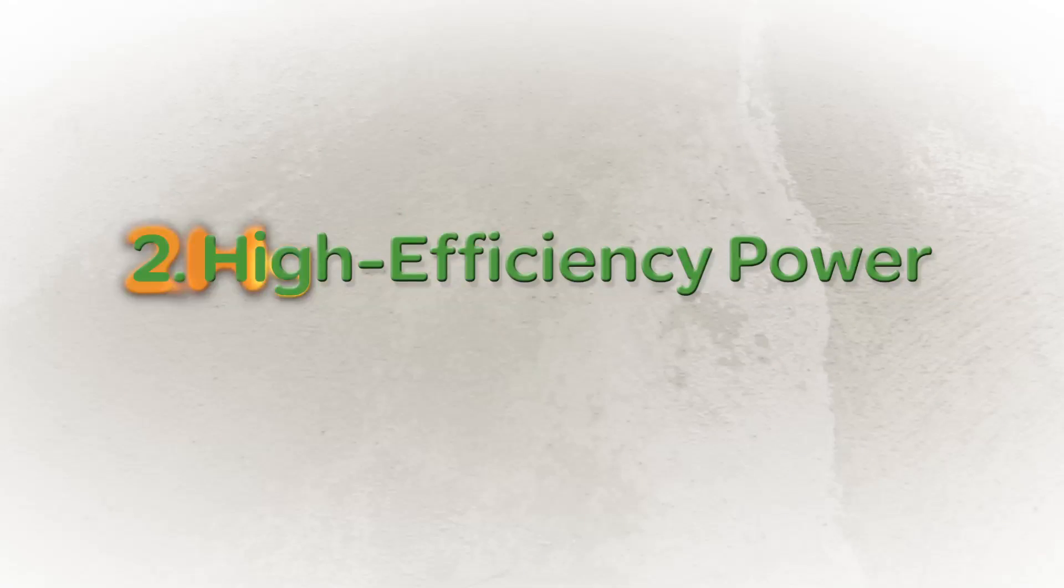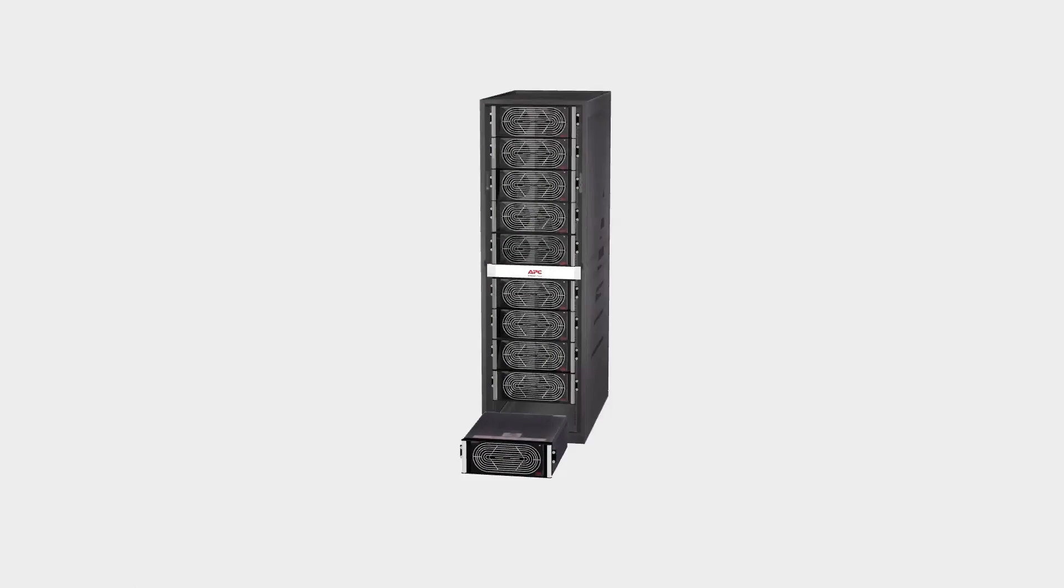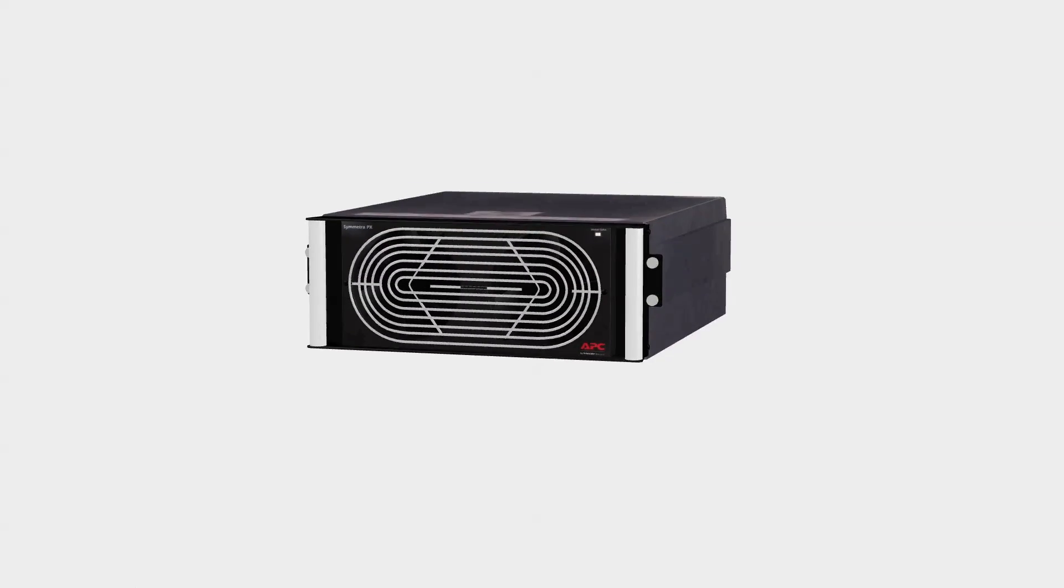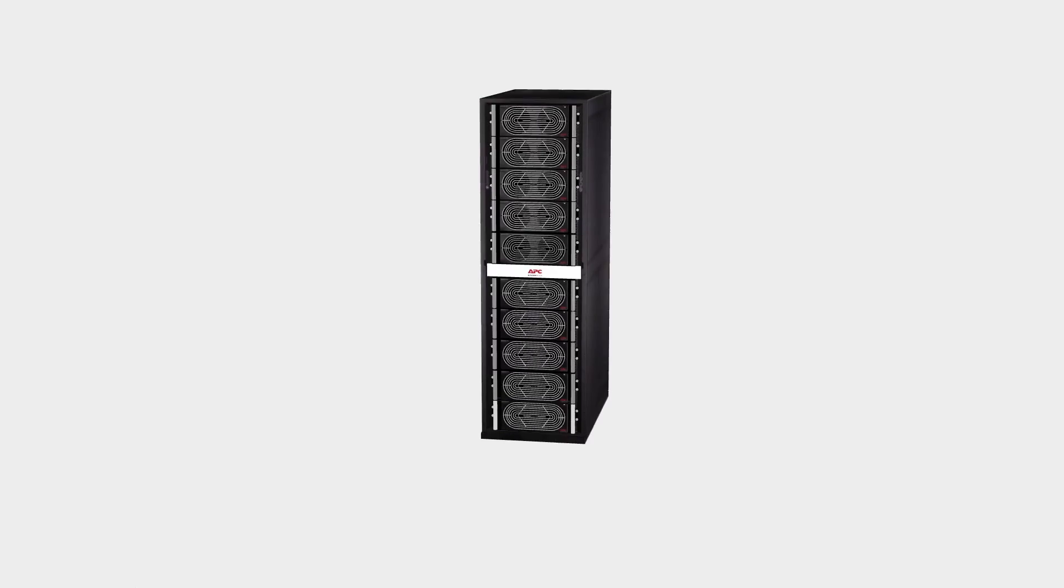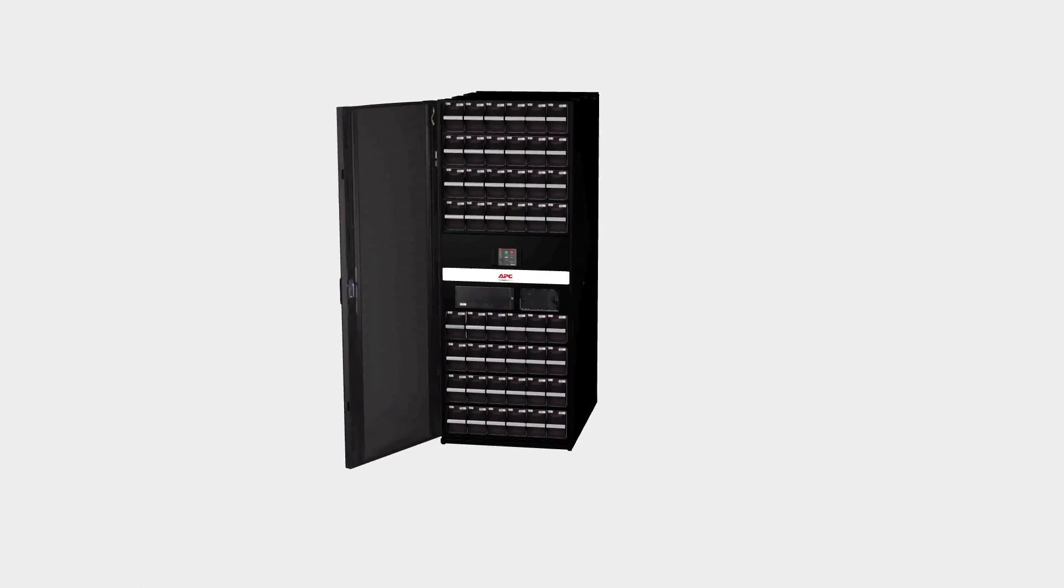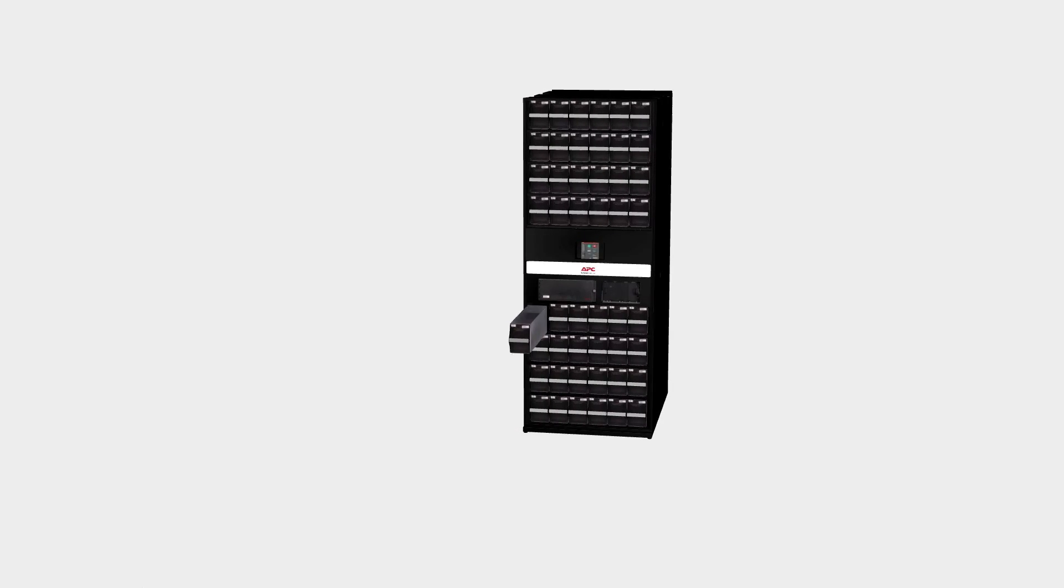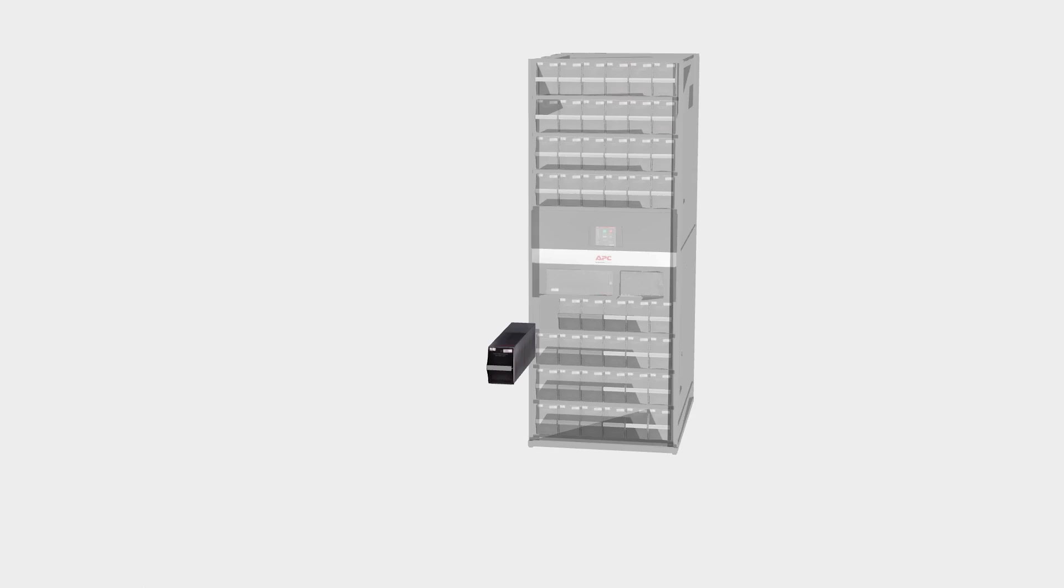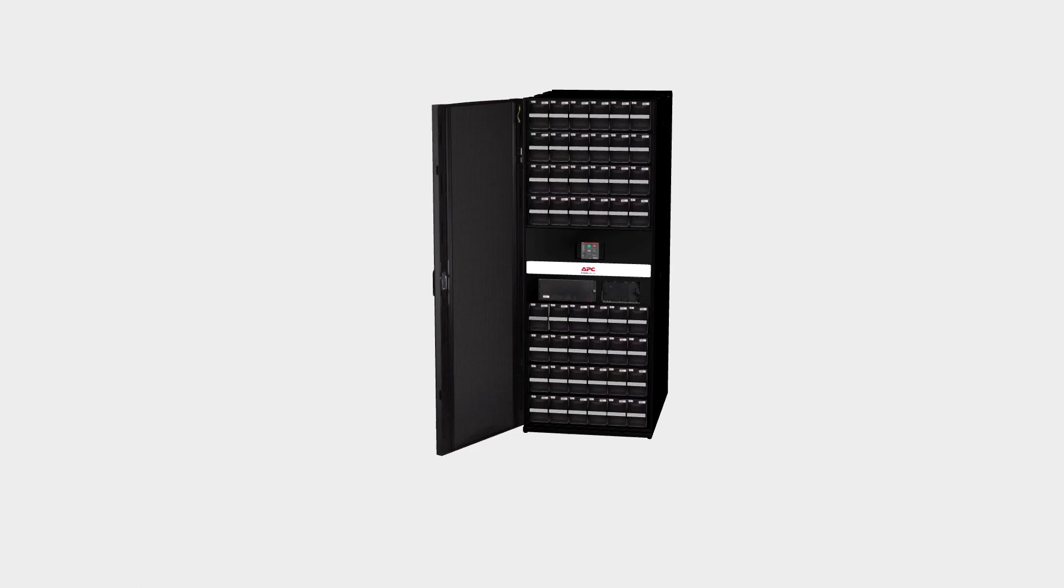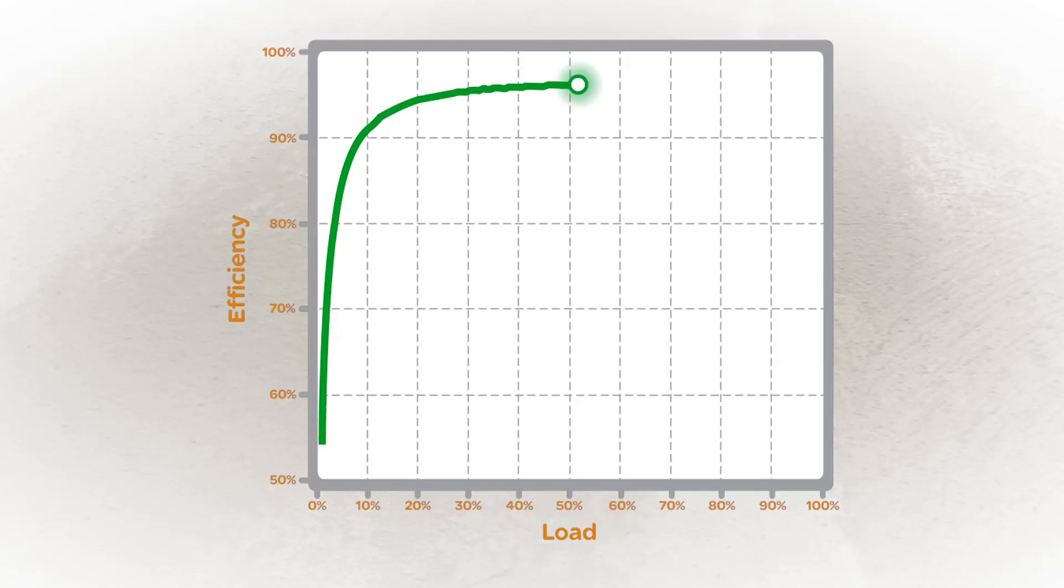Take UPSs, for example. Highly efficient, modular UPSs provide an effective power solution. Hot-swappable, scalable, and less expensive to maintain, modular UPSs allow you to add right-size capacity or redundancy on the fly, making them ideal for virtualization. Some high-efficiency models have 70% less loss than legacy UPSs at typical loads.